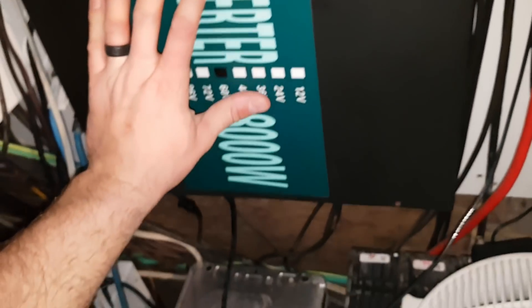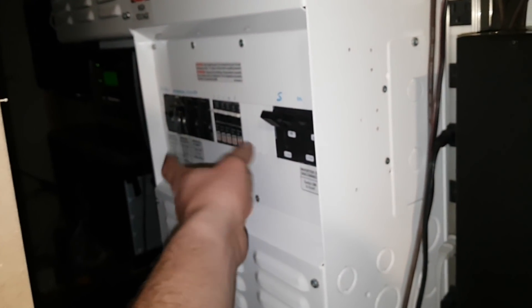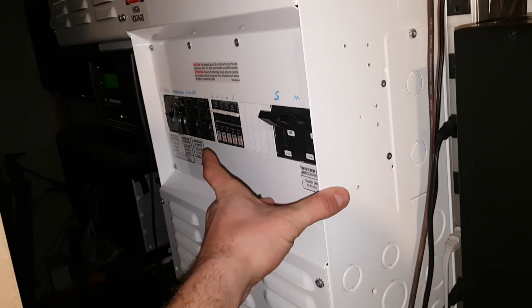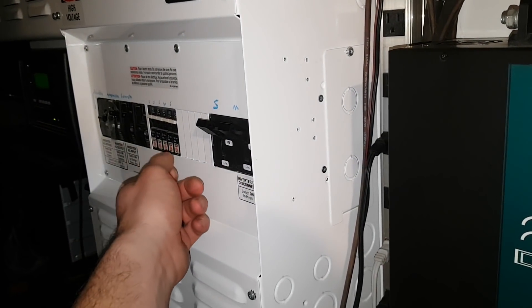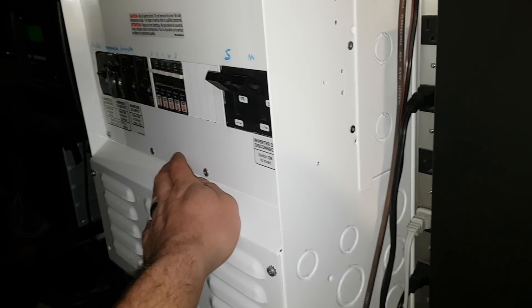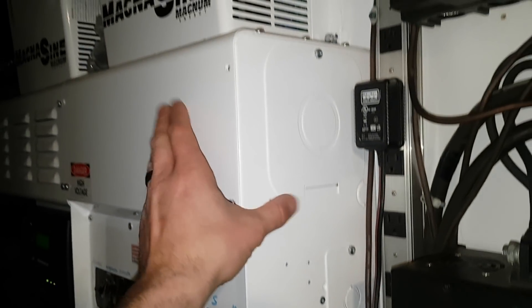Not running off the Reliable at the moment just because the Magna signs are nice — you've got the transfer switch, I can switch everything over really easily. I also have the breaker so I can use the Magnasine. Usually if we're running off-grid and we don't have enough sun, I have the Magnasine set up as a UPS. When the grid goes down everything flicks over and all we see is a slight flicker in the lights — then we're completely off-grid.